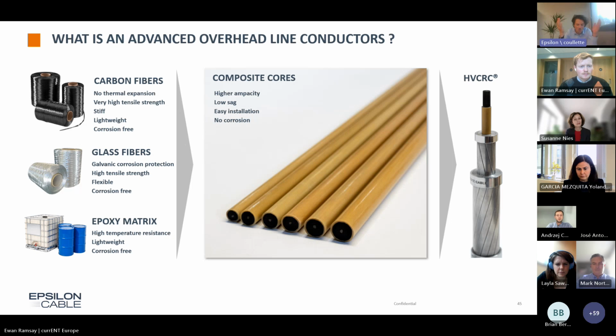Next slide please. You all know about ACSR, the standard aluminum conductor steel reinforced, but probably you haven't heard yet about composite reinforced conductors such as HVCRC. What is a composite advanced conductor? It's a combination of high strength carbon fiber, insulating glass fiber, and high temperature epoxy chemical system. By combining these three elements through the pultrusion process, it's possible to produce a composite core, which is the backbone of this new generation of high temperature, low sag conductor, shown on the right-hand side.